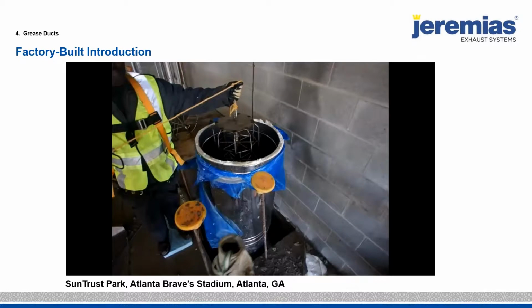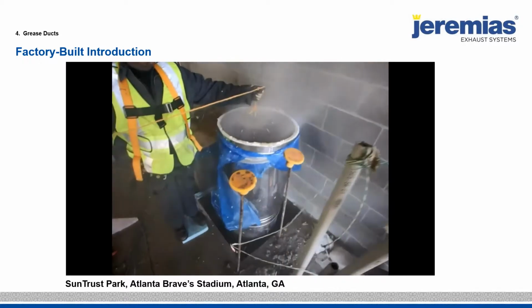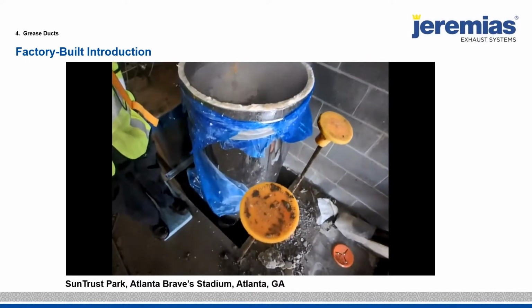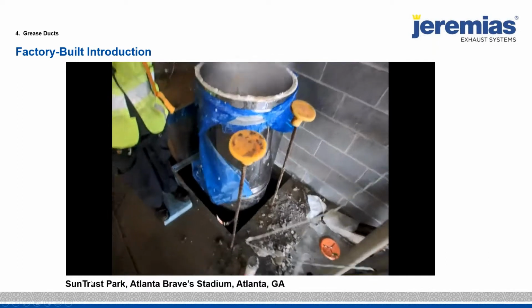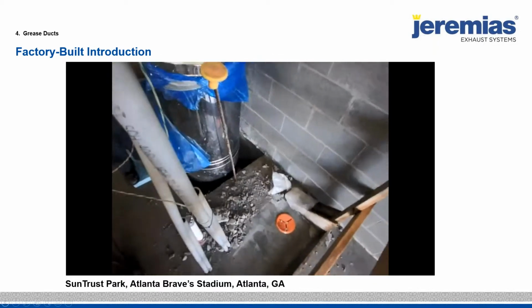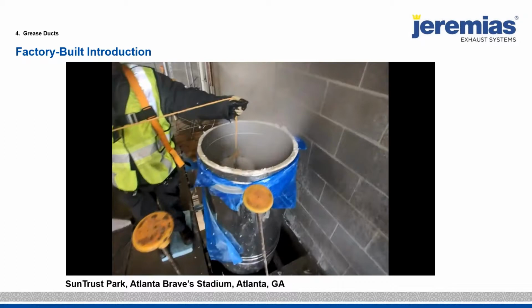And I wanted to show you, this is how folks are, most of the time, cleaning ductwork systems today. So this is a high pressure steam jet of about 1,500 feet per minute, I'm told. And they went through the entire ductwork system to make sure there was no leaks. And by the way, they did find 2 leaks on that 5,000 feet, but they were very impressed. The low sections that were coupled was easily fixed in the field. But they said typically when they high pressure steam jet these grease duct systems on a welded steel stack, they see these leaks every 15, 20 feet.